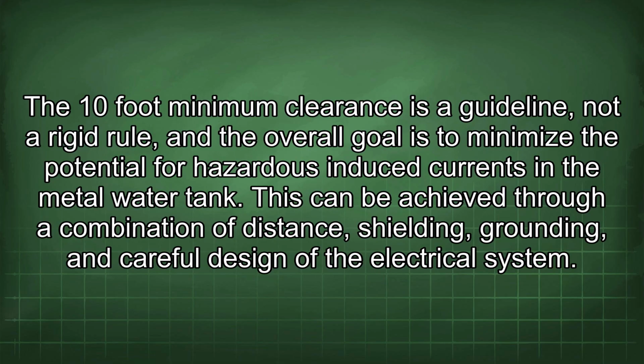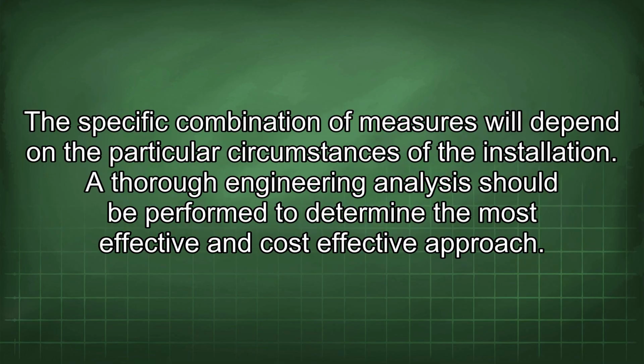A 10-foot minimum clearance is a guideline, not a rigid rule, and the overall goal is to minimize the potential for hazardous induced currents in the metal water tank. This can be achieved through a combination of distance, shielding, grounding, and careful design of the electrical system. The specific combination of measures will depend on the particular circumstances of the installation. A thorough engineering analysis should be performed to determine the most effective and cost-effective approach.